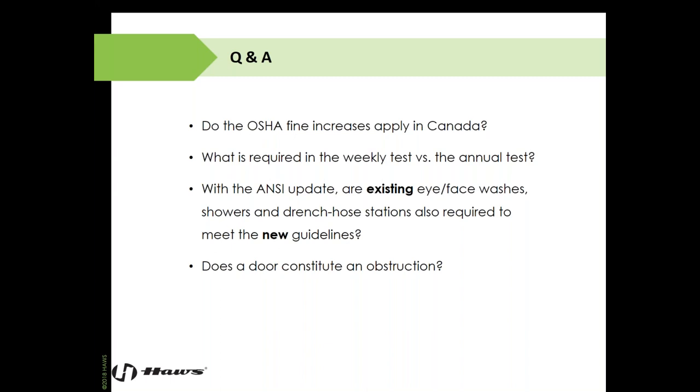What is required in the weekly test versus the annual test? Even though I end up covering it in the webinar, this question gets asked all the time. So weekly tests, again, turn on the equipment, make sure that the eye wash or the eye face wash and the shower have water to the heads of the device, and then make sure it runs long enough to clear out the dead leg.